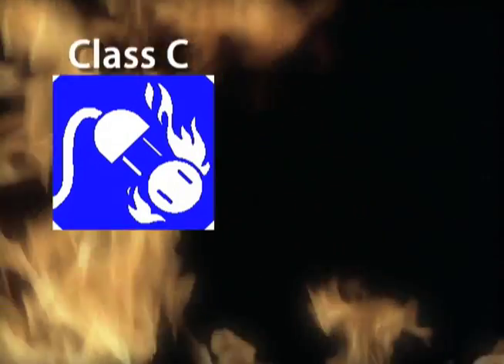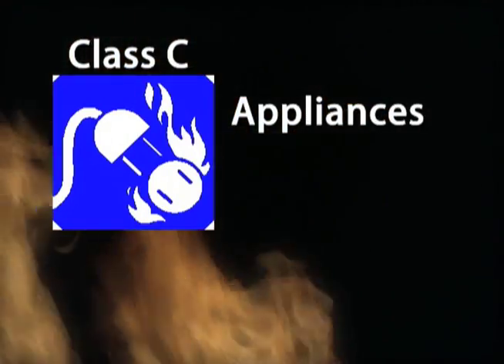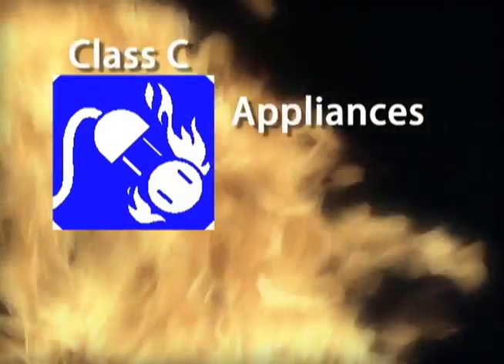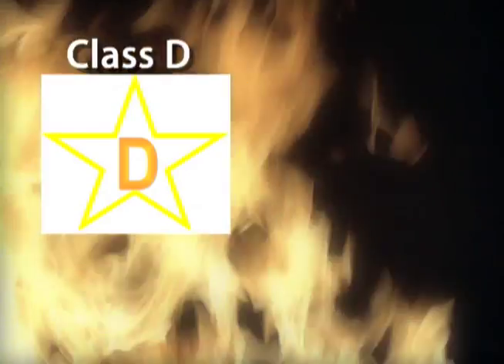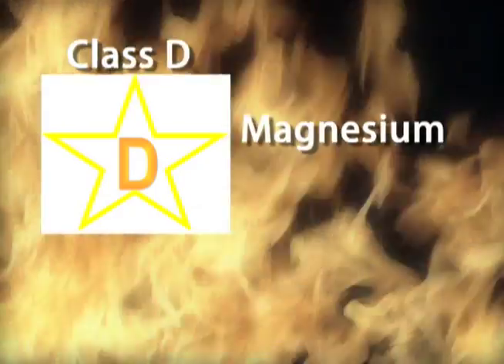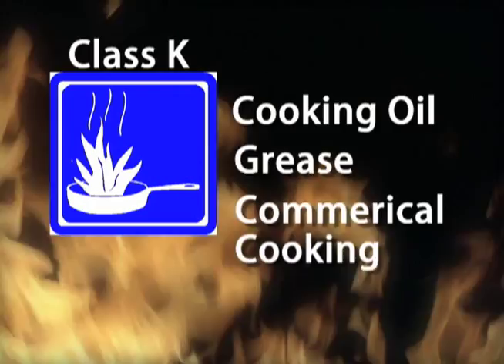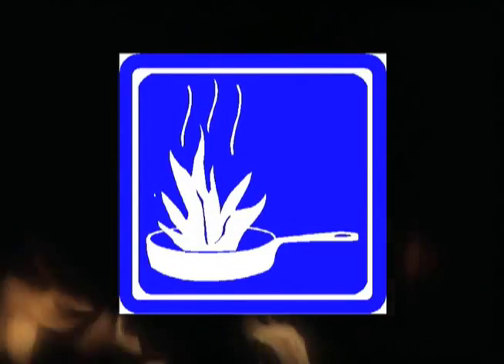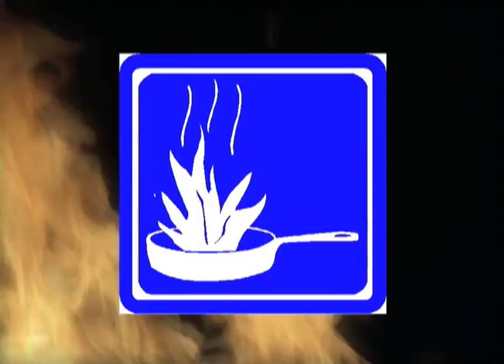it. Class C fires involve electricity. If you have a fire that involves an appliance or a piece of equipment that has electricity going into it or through it, a Class C fire extinguisher is what you're going to need. The symbol for Class C on a fire extinguisher is a picture of an electrical plug with a fire around it. Class D involves combustible metals, such as magnesium or sodium. The symbol for Class D on a fire extinguisher is a star with a D in the middle of it. Class K involves large amounts of cooking oil or grease in a commercial cooking environment. The symbol for Class K on a fire extinguisher is a picture of a frying pan on fire.